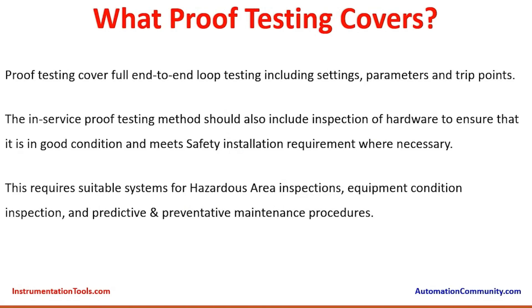What does proof testing cover? Proof testing covers full end-to-end loop testing including settings, parameters, and trip points. In the proof testing, the internal settings of the sensor electronics and parameters — such as constants and damping settings for some instruments — have to be re-verified as per the design conditions. The trip points in the logic solver will be re-checked, because during plant commissioning there is a set value configured for tripping, but during operation there could be reasons to slightly adjust the set points, which must be kept within limits and updated in the records.